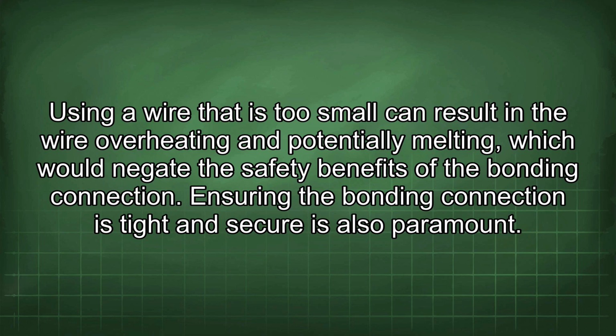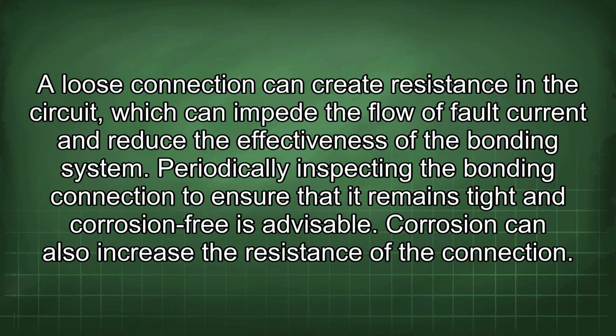Ensuring the bonding connection is tight and secure is also paramount. A loose connection can create resistance in the circuit, which can impede the flow of fault current and reduce the effectiveness of the bonding system. Periodically inspecting the bonding connection to ensure that it remains tight and corrosion-free is advisable. Corrosion can also increase the resistance of the connection.